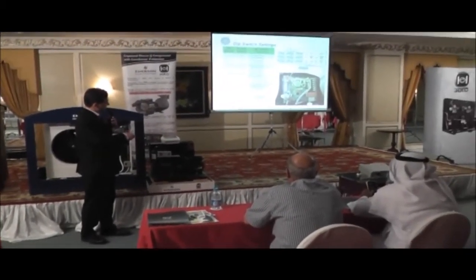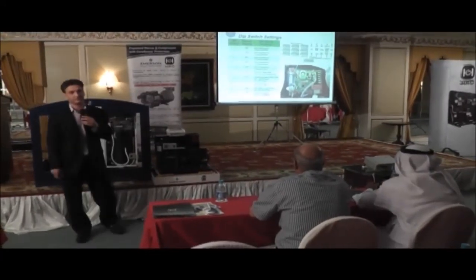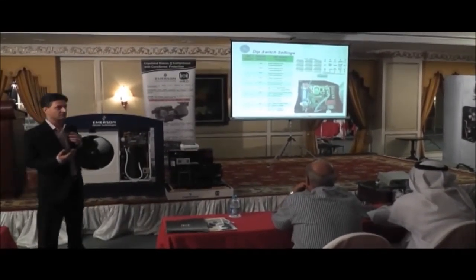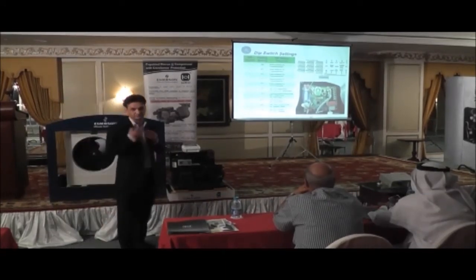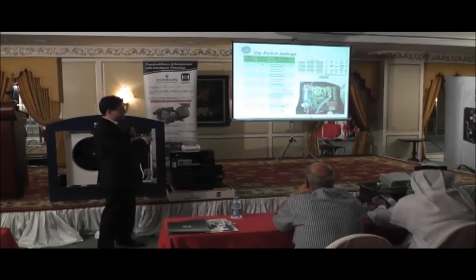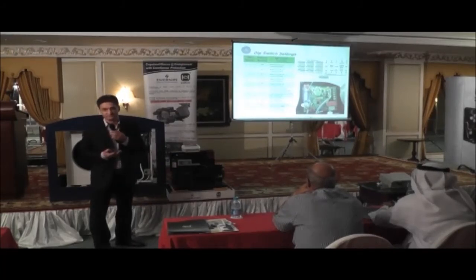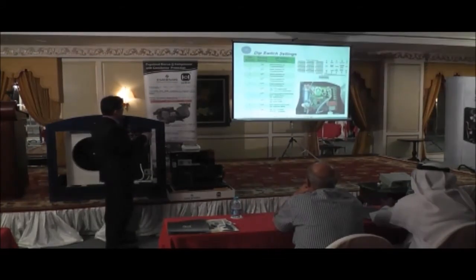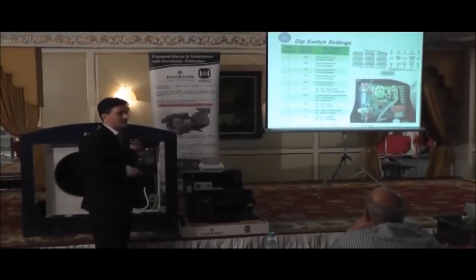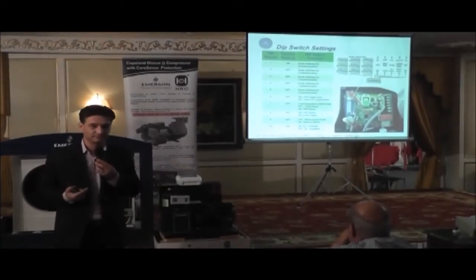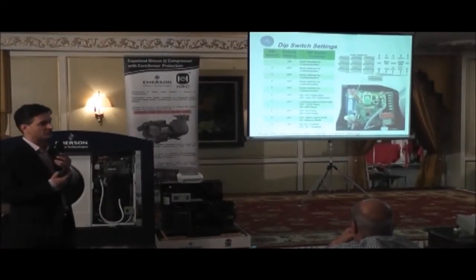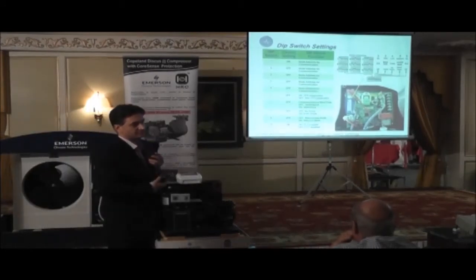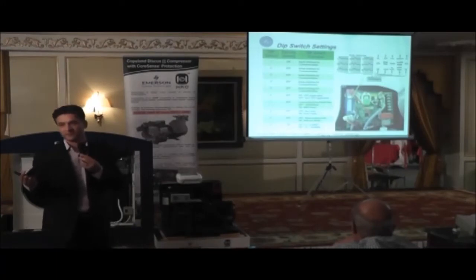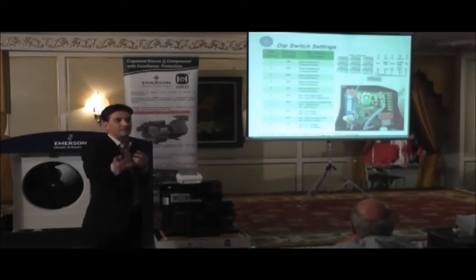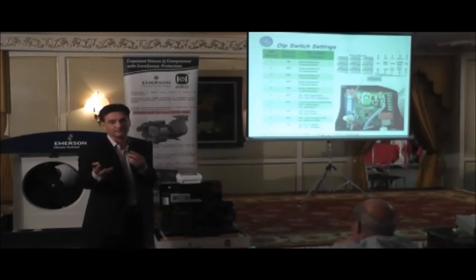The last component I want to talk about on this module is the dip switches. Okay. Now when you get the compressor supplied to you, the dip switches are set in default. Alright. So these will need to be changed depending on how you use the compressor in your system. So if you look at dip switch 1 through 5, if you're going to use this compressor on a rack, and if you have a rack controller that has got Modbus communication, you can then talk with that supplier. We will provide the Modbus code to him. He can upload that onto his controller, and it will basically upload all the information from the compressor.